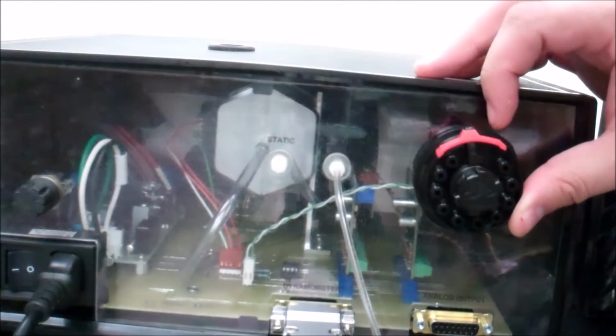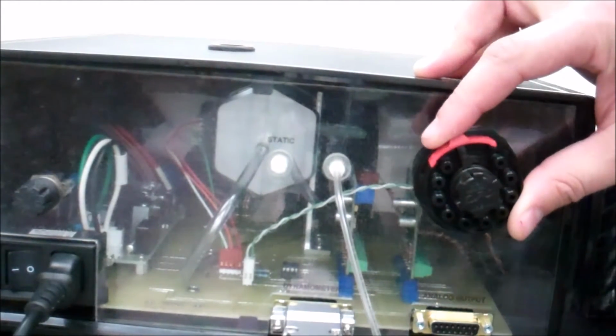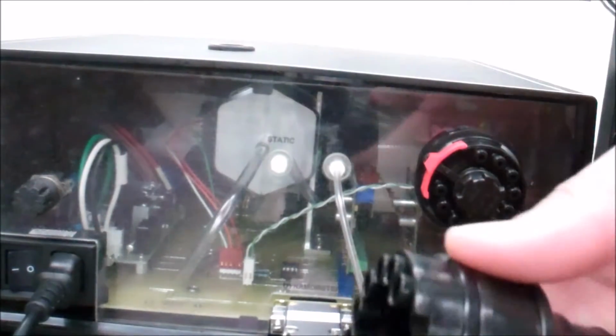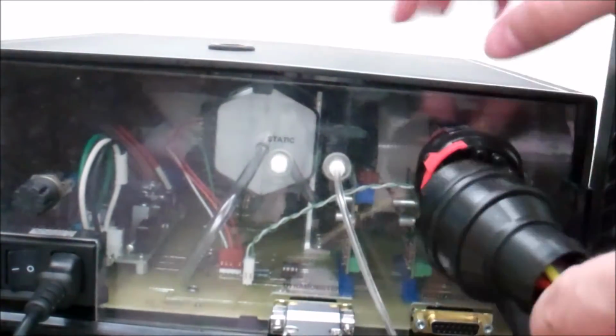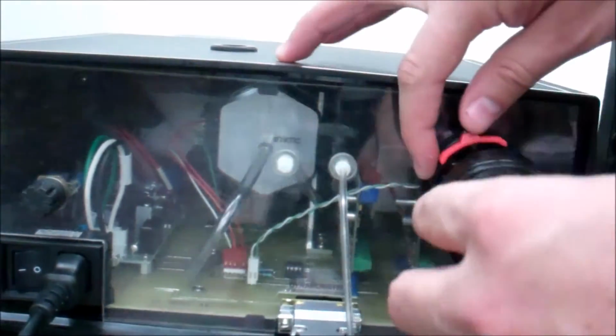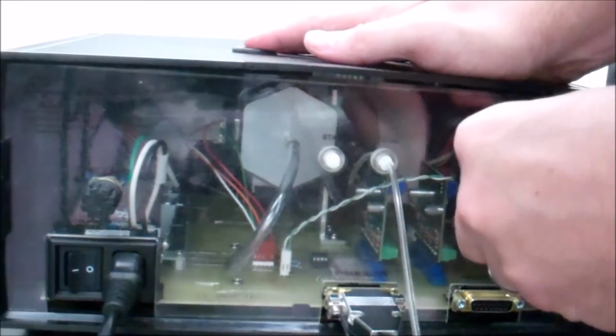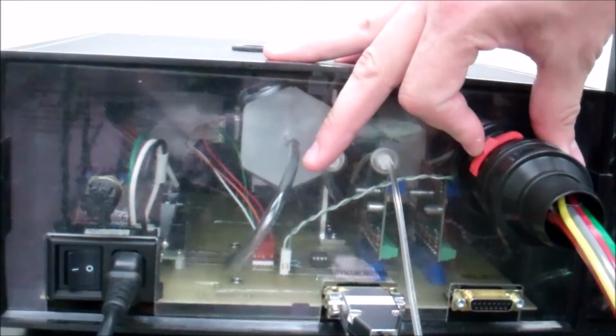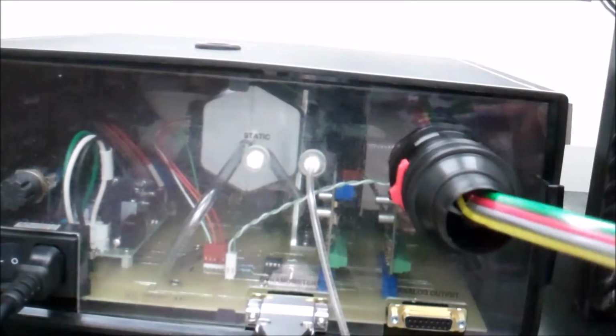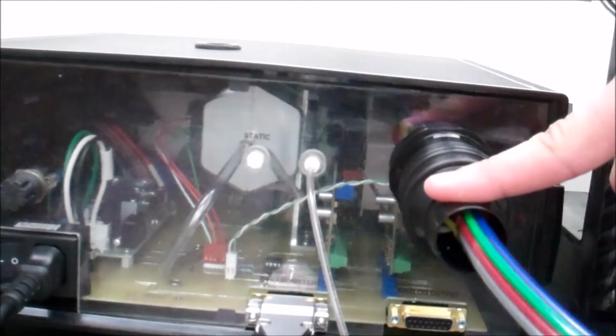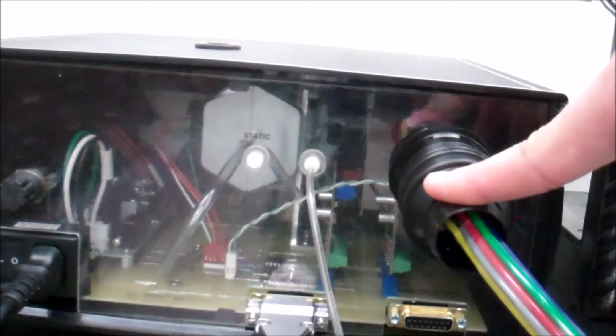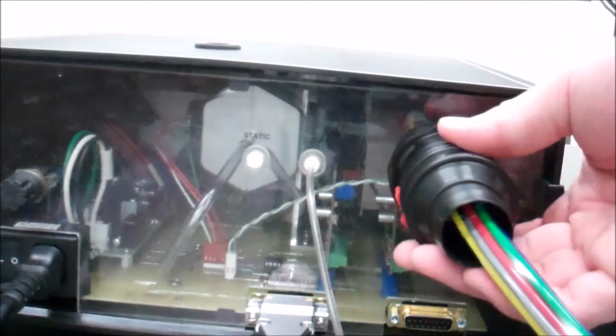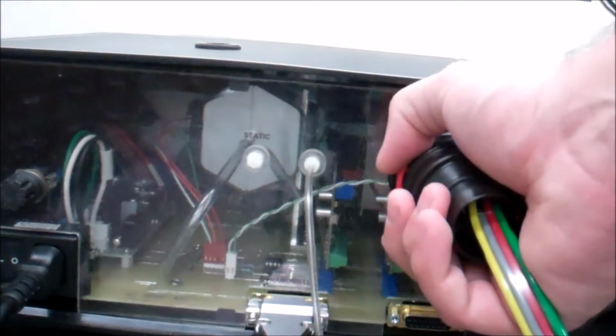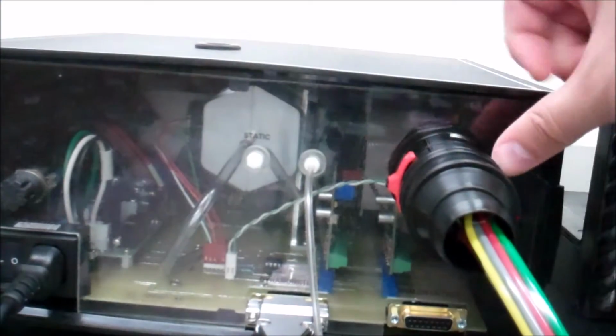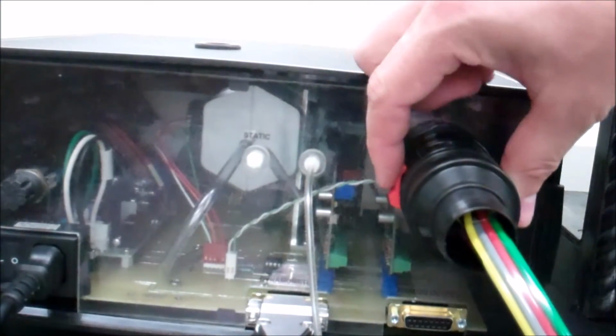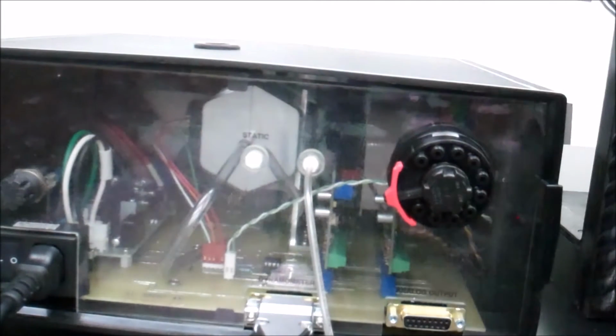You make sure this is turned to unlock or open by shifting the red lever to the left. You orient this top part up with the red section. You push it till it clicks, and then you turn the lever right to lock it. So there are 9 tubes in this connector that you can connect to the airfoil itself for the pressure distribution, or you can use the manometer for that part. To undo this, you turn the red lever to the left, and you just pull the unit out.